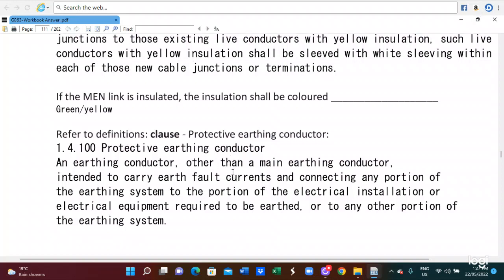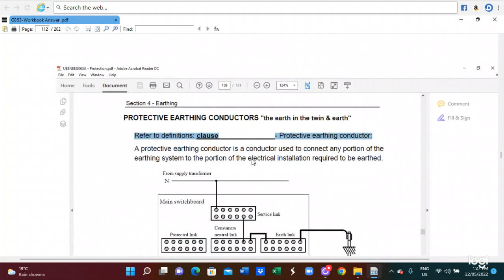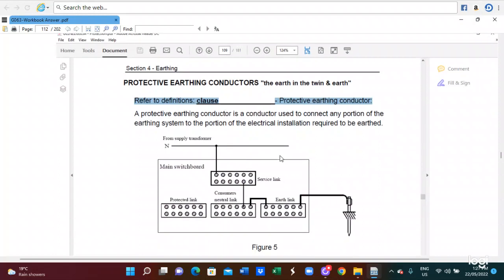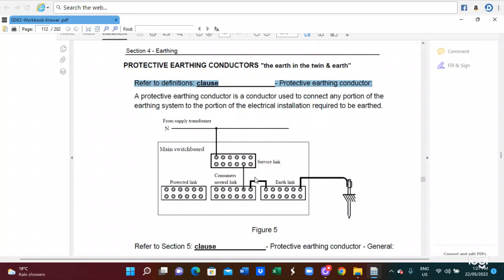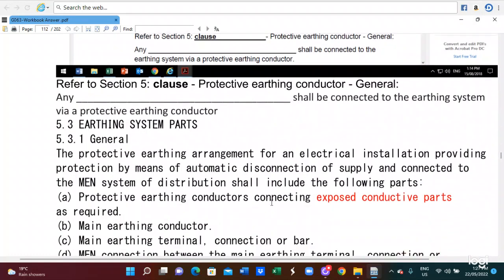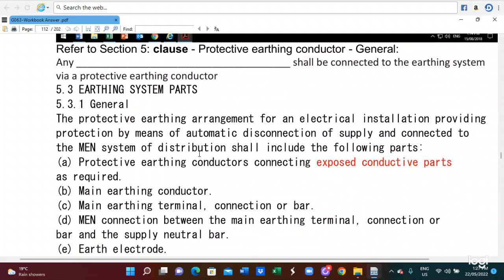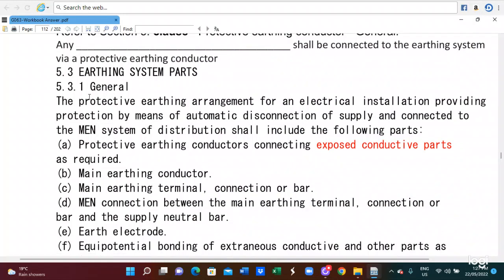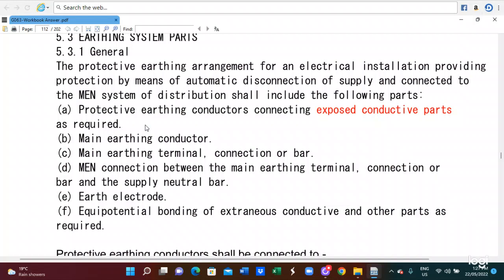And the protective earthing conductor you can see in clause 1.4.100, the protective earthing conductor. To see the protective earthing conductor diagram, you can see Figure 5. The earthing system parts you can see in clause 5.3.1. So they are the earthing system parts. They are the protective earthing conductor connecting the exposed conductive parts, the main earthing conductor, the main earthing terminal or connection bar, and the bonding connection between the main earthing terminal and the electrode, equipotential bonding.